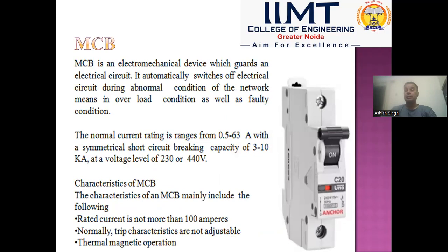The third switching device used in LT switchgear is MCB. MCB stands for miniature circuit breaker. MCB is basically an electromechanical device which guards an electrical circuit. It operates manually under normal condition and it automatically switches off the electrical circuit during abnormal or faulty condition in the network, means in overload condition as well as faulty condition.